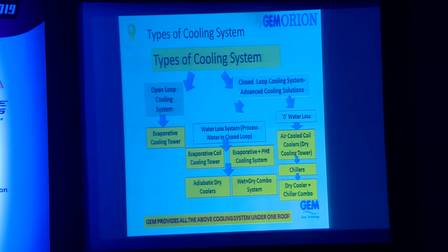When we talk of a closed loop cooling system, we have two specific areas: we can reduce the water loss with some increase in power, or we have a system where we can have a complete cooling system with zero water loss. When we talk of the water loss system in a closed loop, we have two options. One is to use the evaporative coil cooling tower. In the subsequent slides, you will understand what each product means. Then the same concept can be replicated by using a conventional cooling tower with a plate heat exchanger and internal closed loop cooling. Alternately, we can also have an adiabatic dry cooling tower for achieving specific temperatures. Of course, there are some restrictions in each process, which we will highlight during the course of the presentation.